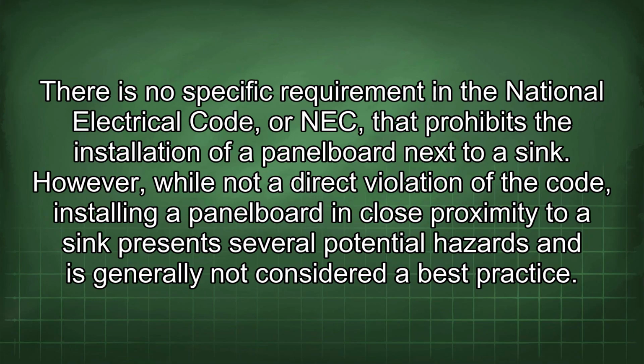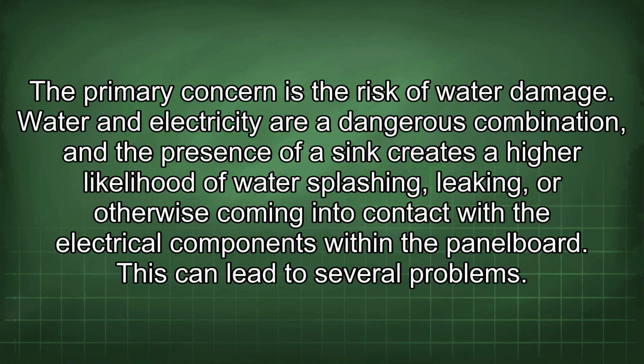There is no specific requirement in the National Electrical Code, or NEC, that prohibits the installation of a panel board next to a sink. However, while not a direct violation of the code, installing a panel board in close proximity to a sink presents several potential hazards and is generally not considered a best practice. The primary concern is the risk of water damage.